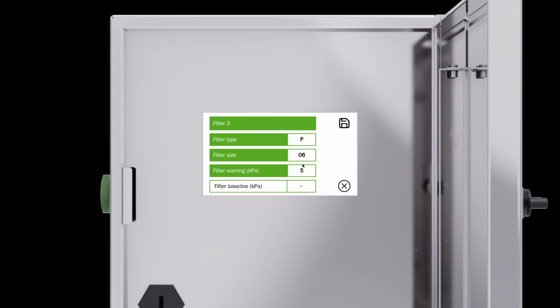The filter baseline is automatically set by the filter monitoring function. When a new filter is installed, the function monitors the conveying operation. It analyzes the data gathered and then, based upon this, sets the baseline value. This ensures that the filter monitoring function adapts to each Piab vacuum conveyor with, for instance, differences in the vacuum pump capacity, the conveyor batch volume, the materials being conveyed, and the geometry and length of the conveying pipeline. Once set, the baseline value represents the filter pressure drop for a new filter for the Piab conveyor.